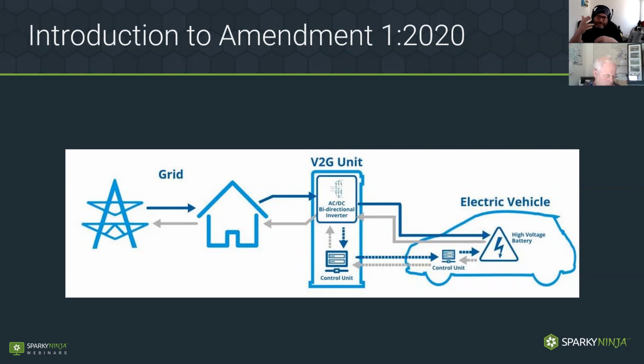Obviously the meter will go both ways with regards to the way the data is analyzed. It'll discharge from the battery, so we will feed back onto the grid. And then at night time, when there's lower demand, we will take that back for a lower rate. So it's supposed to be a good financial solution. It's worth looking into, but this is the point: we're going to go both ways here. This helps with capacity issues on the network grid, which these are going to create by adding loads of demand.